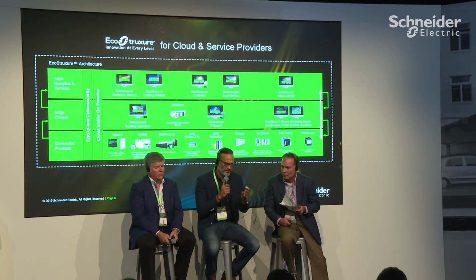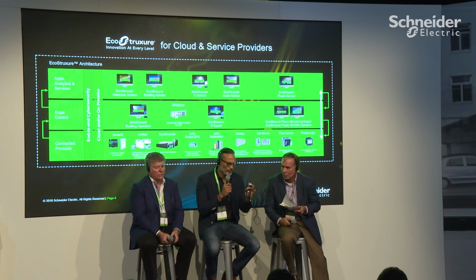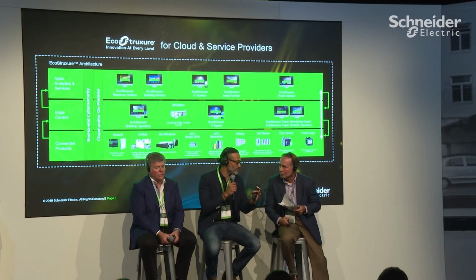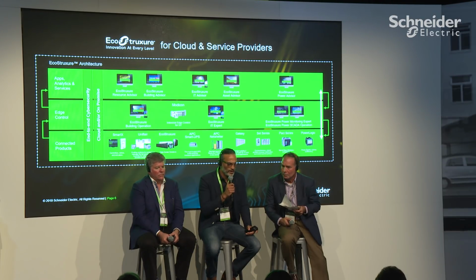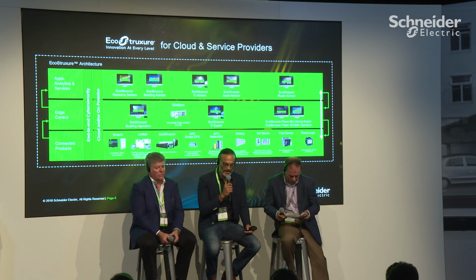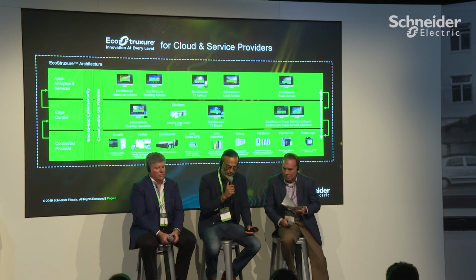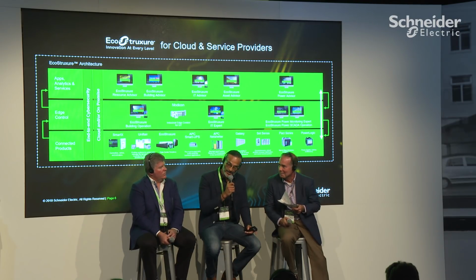I think it's very specific down to the transferability of the data, or traceability might be a better description. What I mean is, I can go up to a piece of equipment in a data center that's in operation, and through our maintenance systems find out everything I need to know about it for the duration of its service life. If I'm good, I can access commissioning data. If I'm very good, I can access installation-related data.